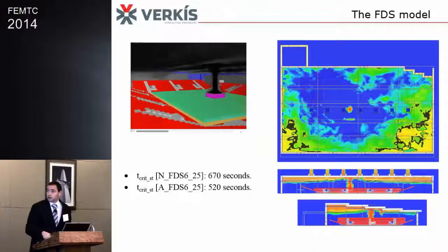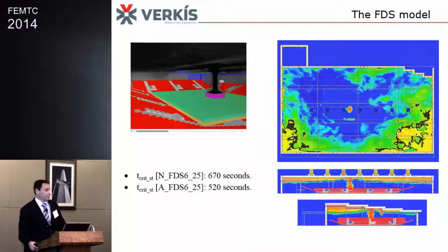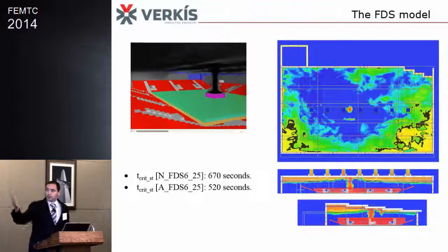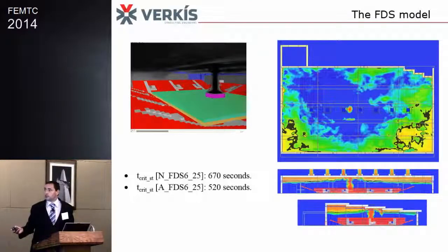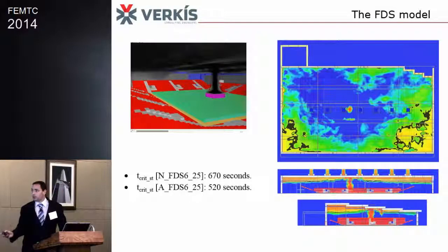So I've calculated now, this is parallel computation. Here on the left, this is the point of view of the little guy standing at the top of the highest row. He will have his face very quickly facing the smoke. And also, this is the visibility at 2 meters above the highest row. So I want people to evacuate before they meet this.